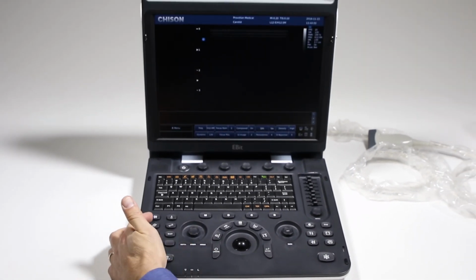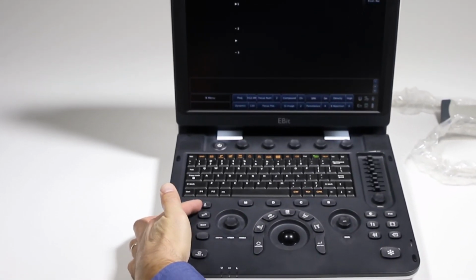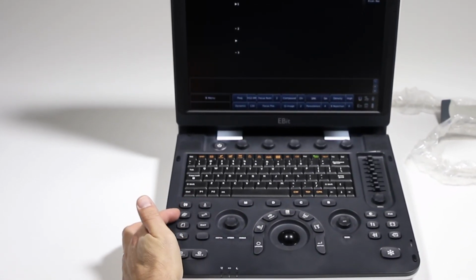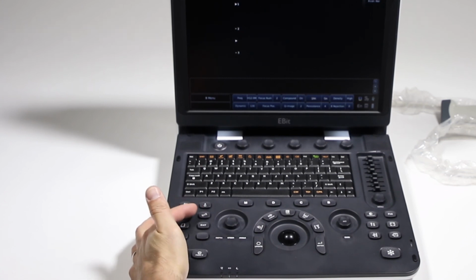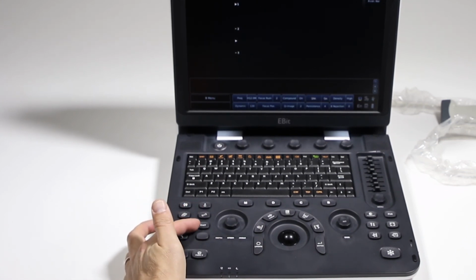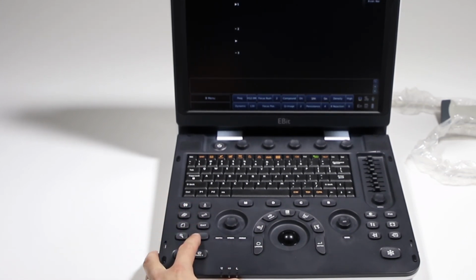Here we have our exam function group, your patient, your probe or preset select, archive, your setup to get into the system menus, report page, exit, zoom, and this is a custom programmable key, just as there are some up here as well. Print 1 and print 2 are also user assigned for whatever printers you might have set up. You can use them for other items as well.